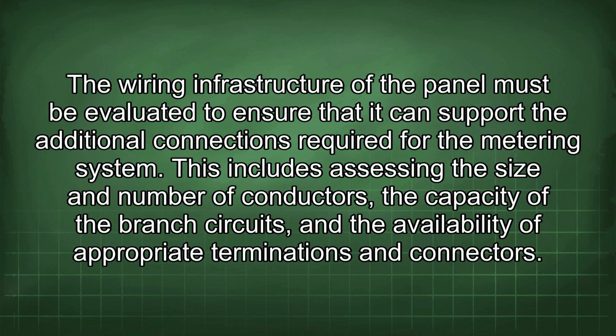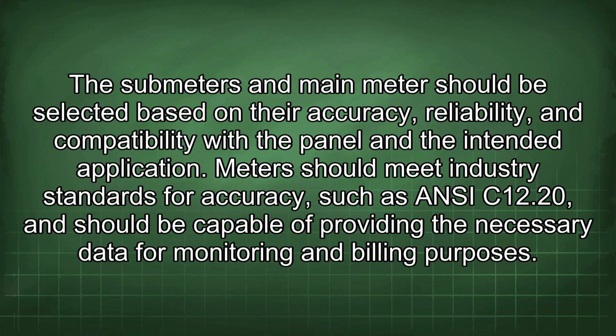The wiring infrastructure of the panel must be evaluated to ensure that it can support the additional connections required for the metering system. This includes assessing the size and number of conductors, the capacity of the branch circuits, and the availability of appropriate terminations and connectors. The submeters and main meter should be selected based on their accuracy, reliability, and compatibility with the panel and the intended application. Meters should meet industry standards for accuracy such as ANSI C12.20 and should be capable of providing the necessary data for monitoring and billing purposes.